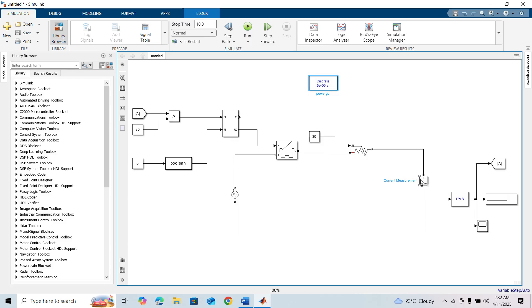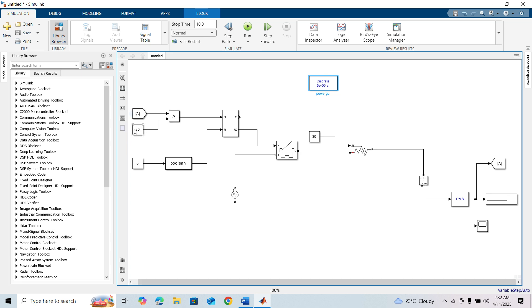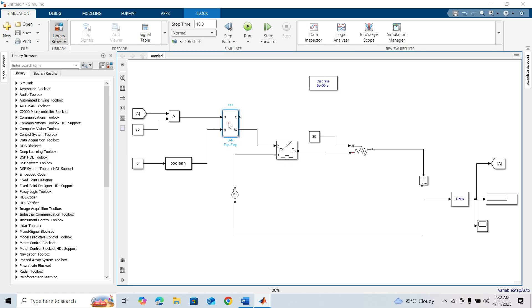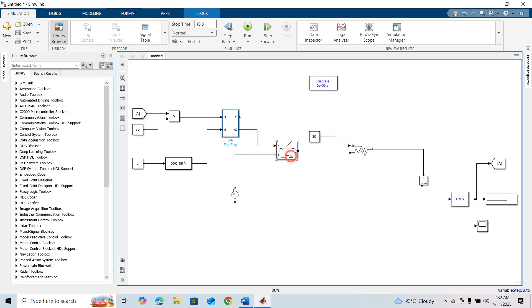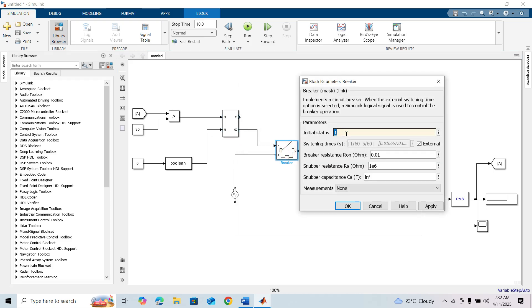Here, the current measurement block measures the RMS current value. The current is compared to 30 amperes. When the current is greater than 30 amperes, the circuit breaker operates. The initial condition is zero, and the breaker initial status is 1.